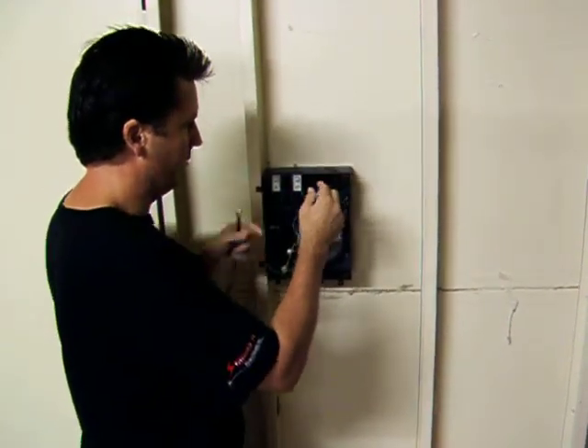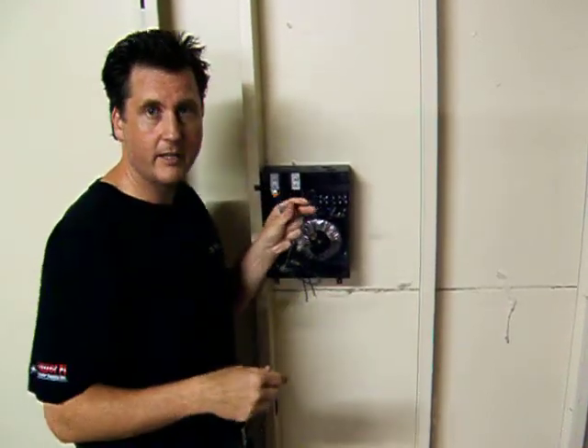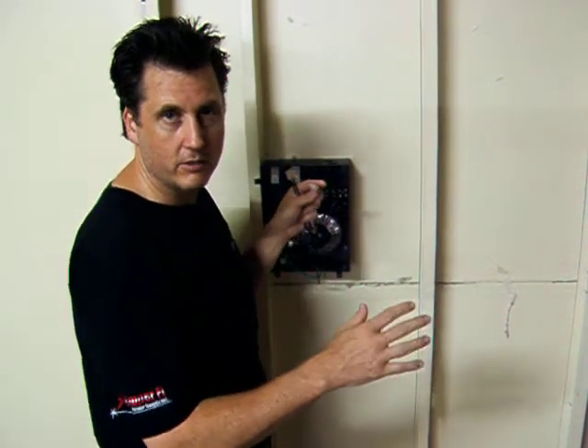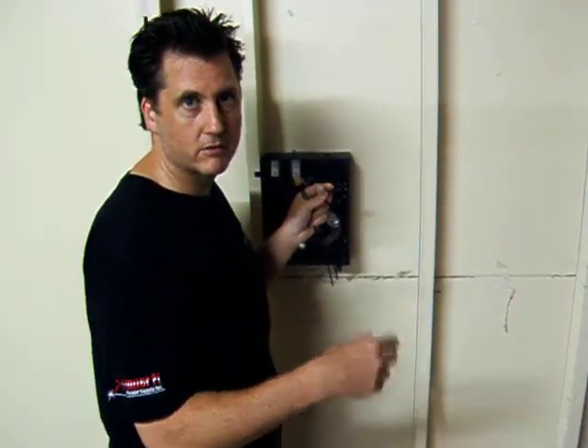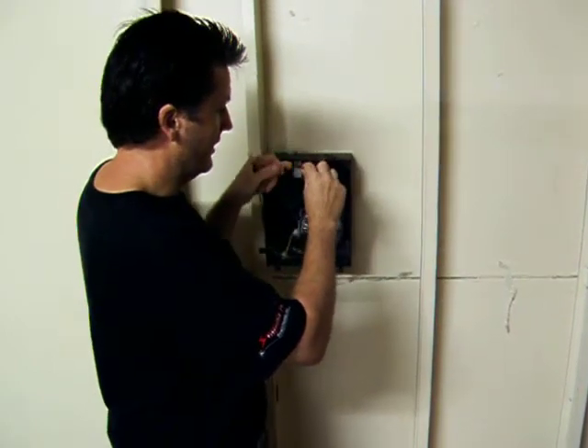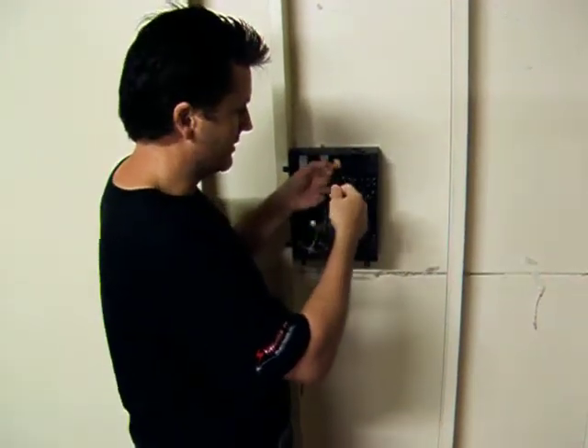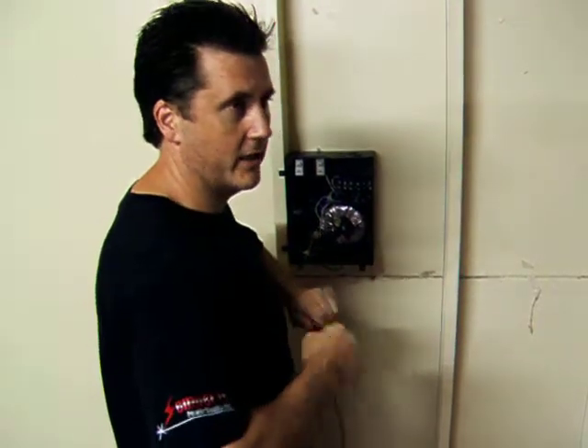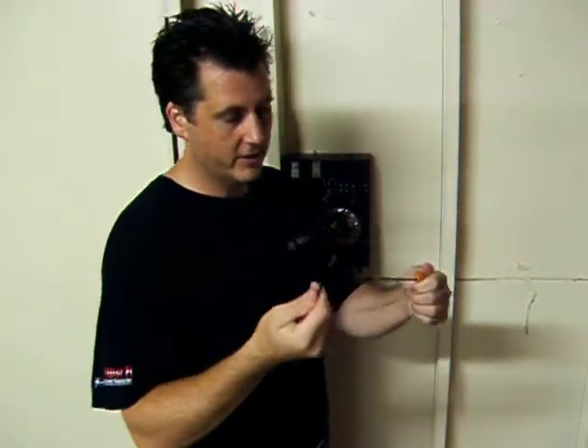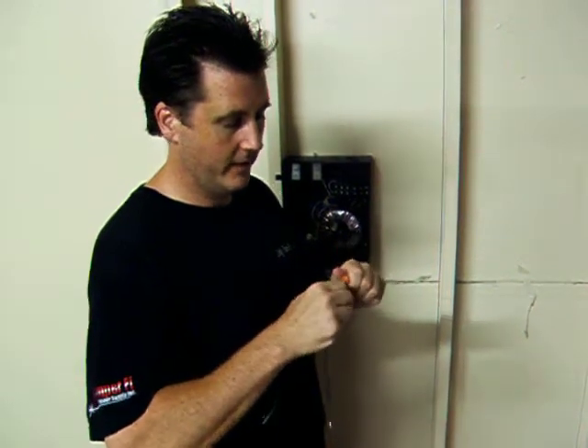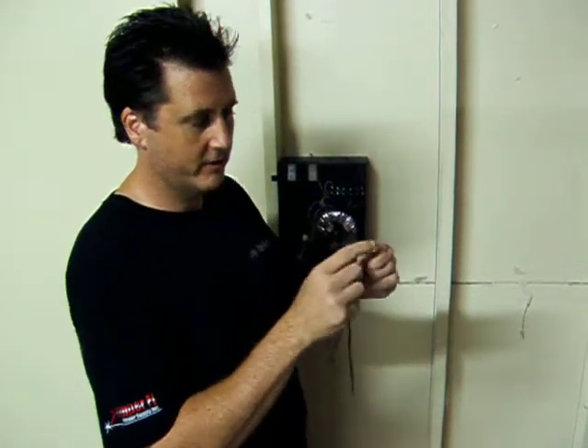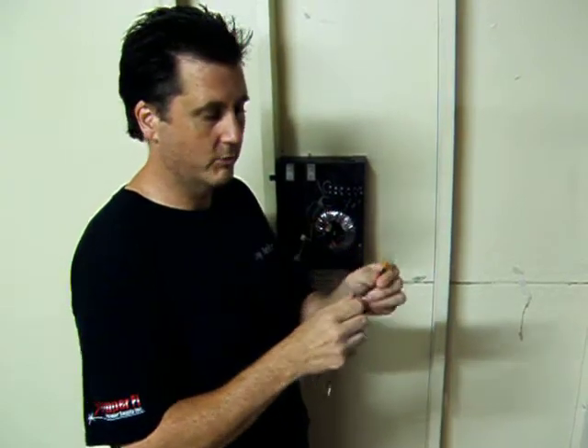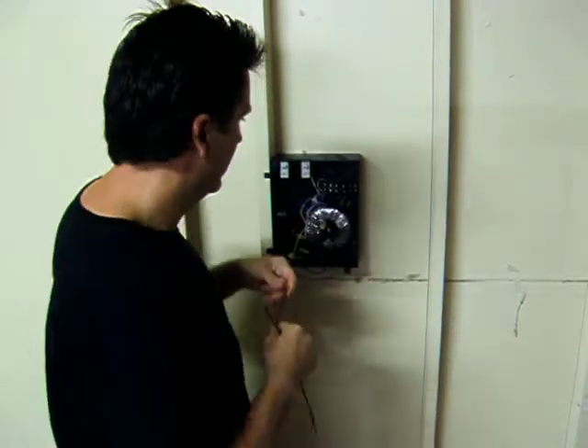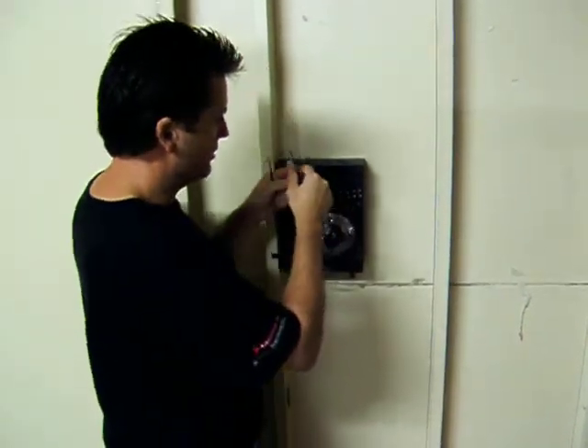In this case, what you would do is it has a quick connect. Again, your lighting, if you have one cable coming back from your lighting, you have two conductors. Your low voltage wiring is not grounded, so one end of your lighting, it doesn't matter which one, would plug into this conductor. Now on these quick connects, all you do is you take your wire, you strip it, and it basically pushes in. You want to push it in until you see it through the clear. You push it all the way up. If you have to remove it, it's simply twisting and pulling. It's that simple. So that end hooks into your circuit breaker.